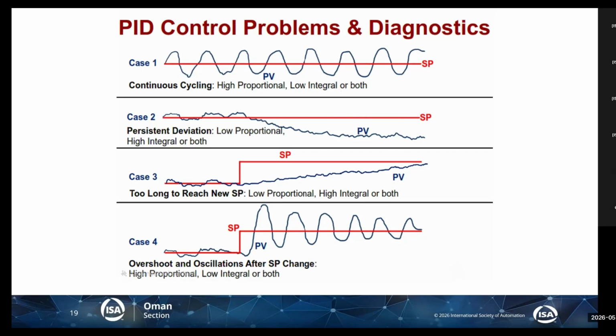Maybe 5 proportional gain on this valve, on this system, will make it steady, and the same 5 on another loop will make it oscillating. So from system to system, it will be different. So if I have a very high proportional number, it will oscillate, or if I have a very low integral. Very low integral means it's impatient. It's repeating the proportional action frequently, consistently.